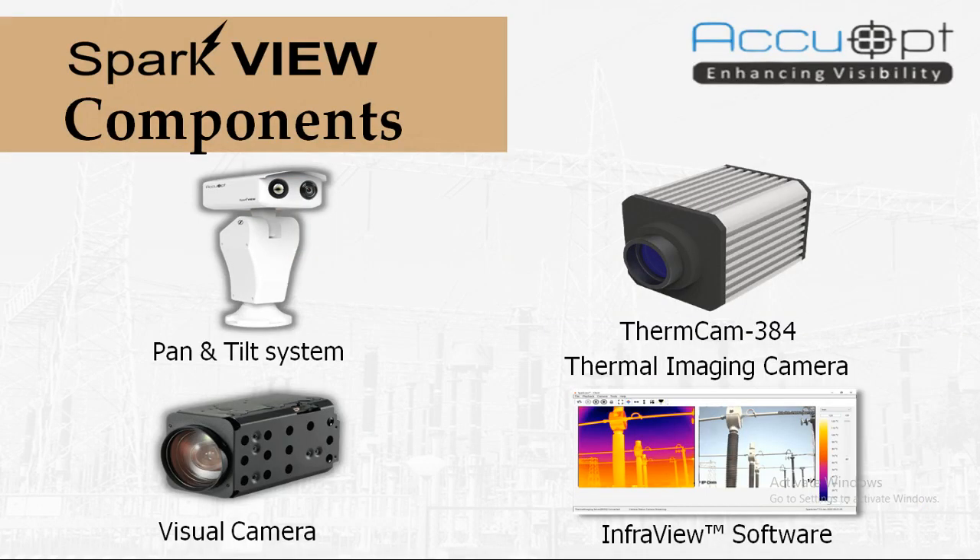The major components of our substation monitoring system are a pan and tilt system, a thermal imaging camera, a visual camera, and our InfraView software. Using only a thermal camera creates difficulty in identifying the exact location of a hotspot, so we also use a visual camera, which enables the user to identify the location with ease. As shown in the picture, SparkView provides both thermal and visual images so one can easily identify the hotspot or faulty area.